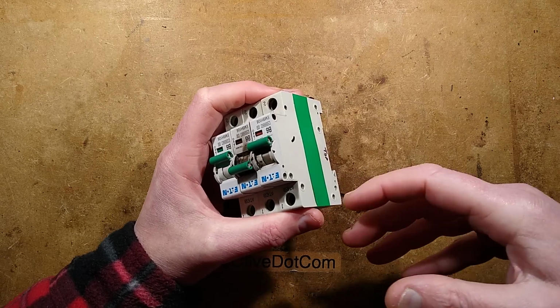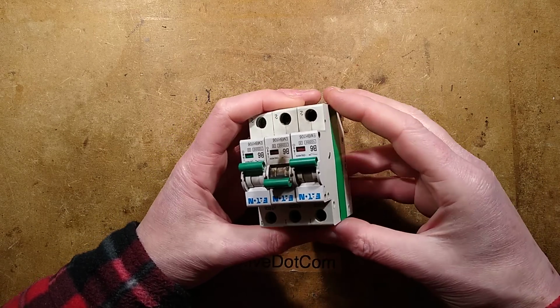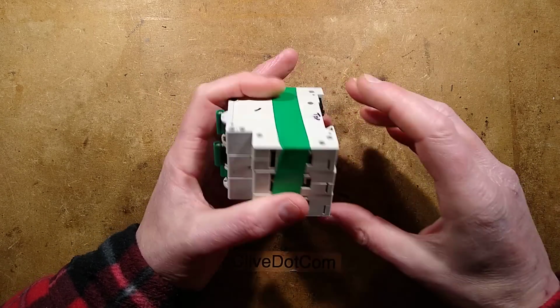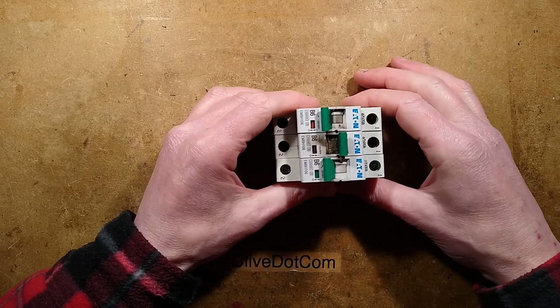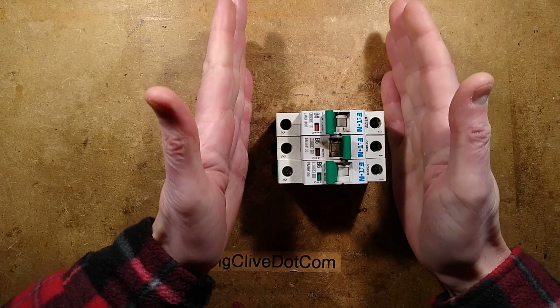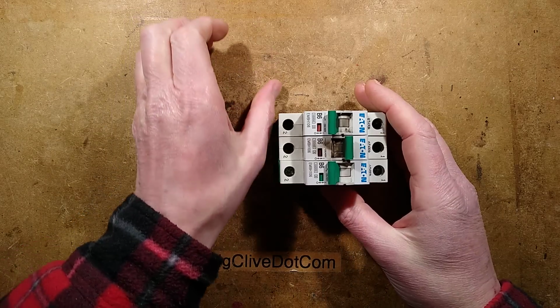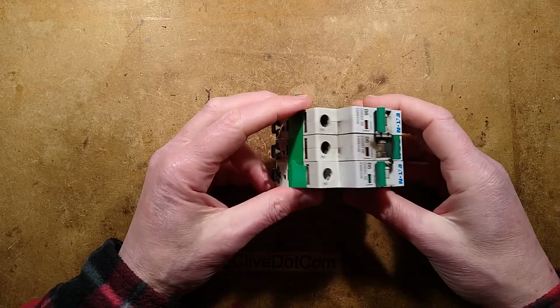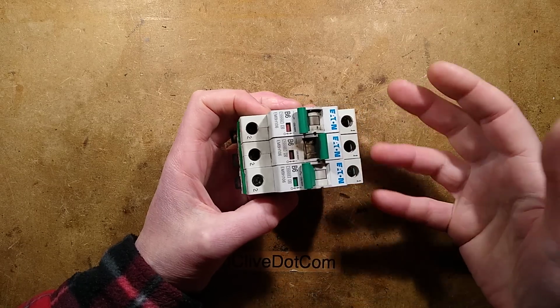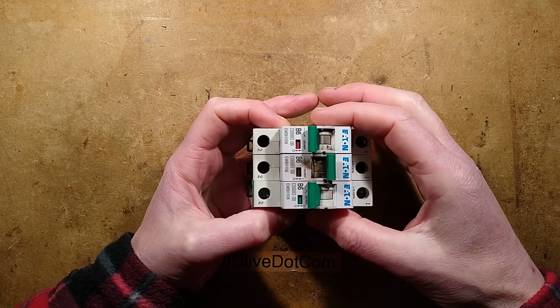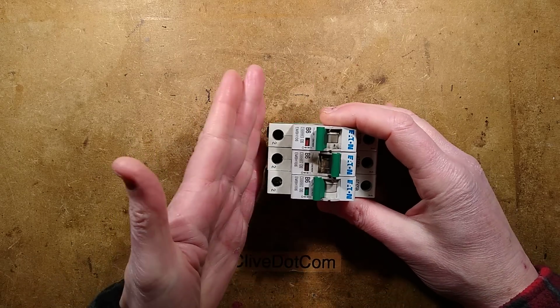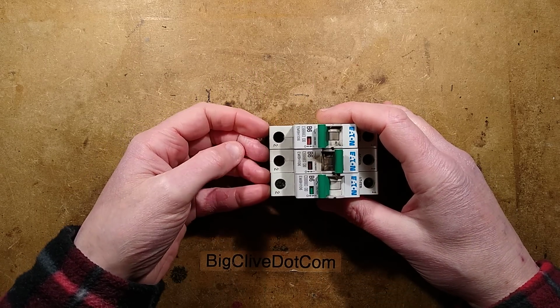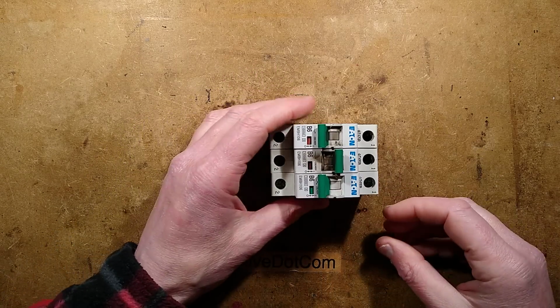So let's open these. Let's take them apart and see what went wrong inside. Back at the bench now, we have the background to this incident, and these circuit breakers are labelled top and bottom, suggesting it was in one of the vertical industrial distribution boards with the busbars down the middle, and that's possibly where a lot of the flashover that triggered the fault of the other breakers happened as well, because you've got basically three phases, 415 volts effectively, between adjacent breakers.